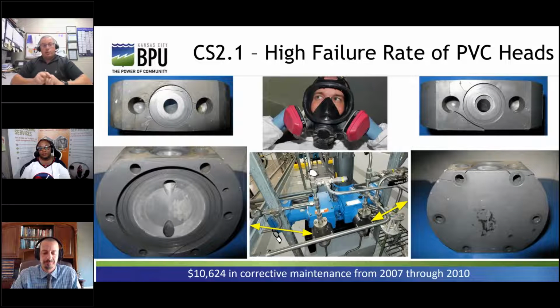Case study 2, high failure rate for PVC heads. Pictured at the center of the slide are an operator with full face respirator and PPE, a metering pump below that, and surrounding images are all 4 sides of a single ammonia metering pump head made out of PVC that had multiple stress cracks from exposure to aqua ammonia. 29% aqua ammonia at that. This was the problem to be solved.